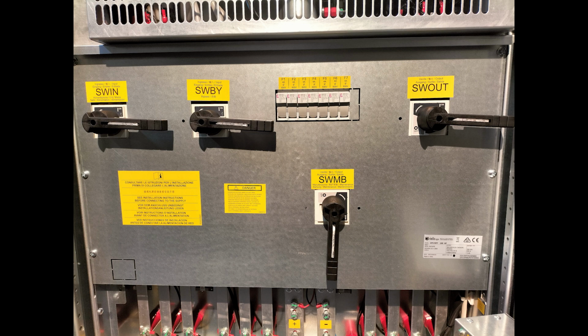The switchgear panel is next. On the left-hand side, the switch labeled SW-in is the main rectifier or main input switchgear. We then have the SWBY, which is the bypass switch input. Next to that, there's a fuse bank for CPU system fans and control system. On the right-hand side, SW out is the main output switchgear. The bottom switch is the maintenance bypass switch, and we'll be discussing that a bit later.